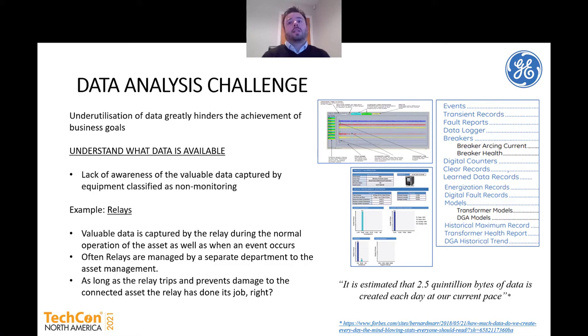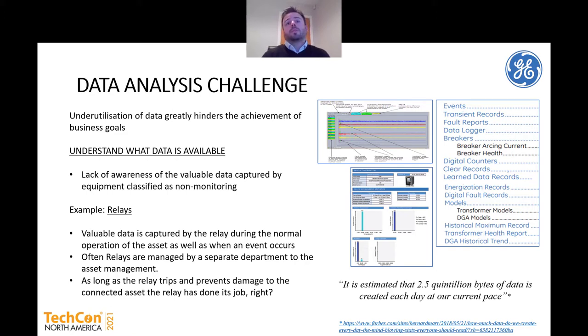There are things like events, transient records, fault reports, breaker records, digital counters, and energization records — a wealth of information being captured by relays that could be analyzed by transformer experts. It's estimated that 2.5 quintillion bytes of data are generated each day globally. The data being generated by grids is increasing exponentially based on the amount of sensors being deployed and enhancements around those sensors. As organizations work with vendors of online monitoring, vendors can use existing sensing technology to capture new types of data, providing more and more information on the asset's condition.